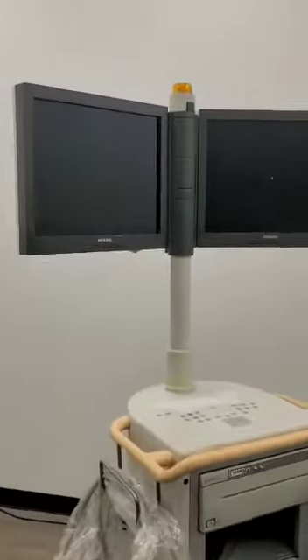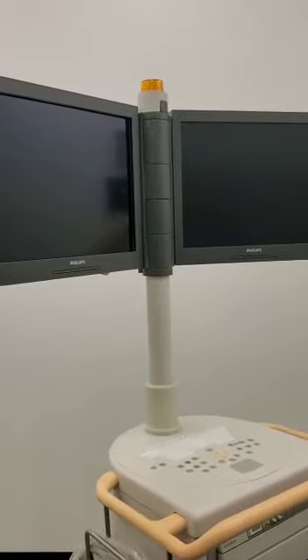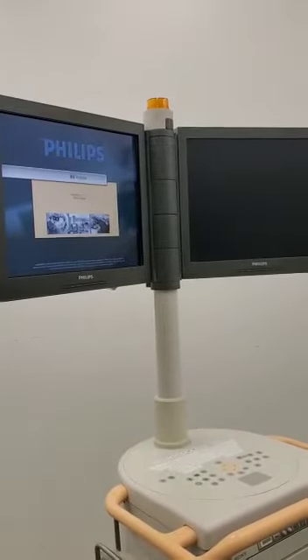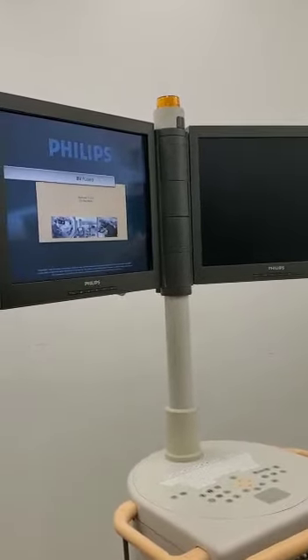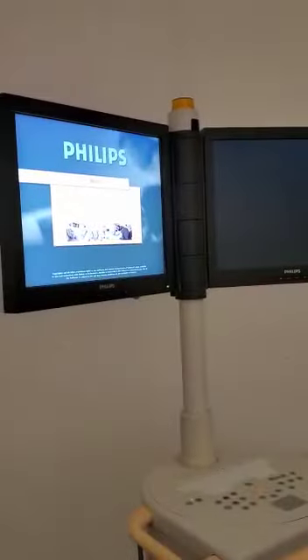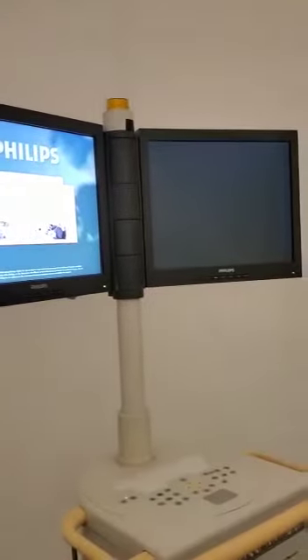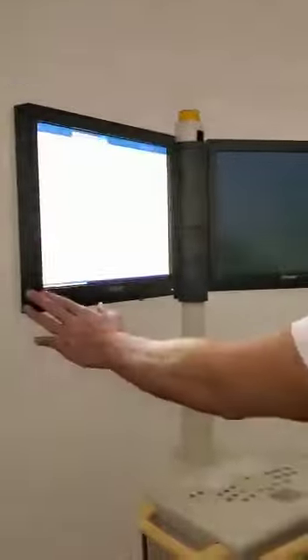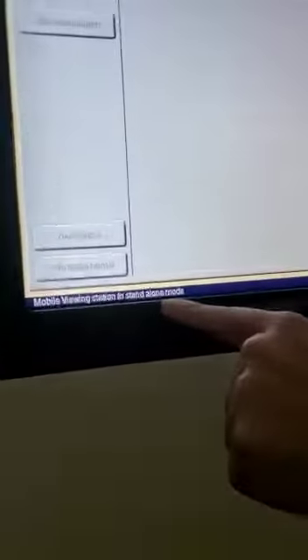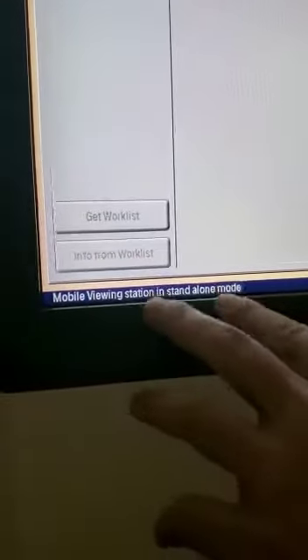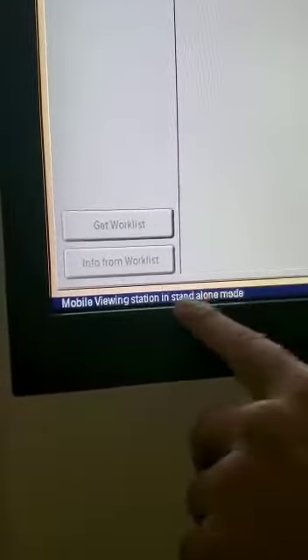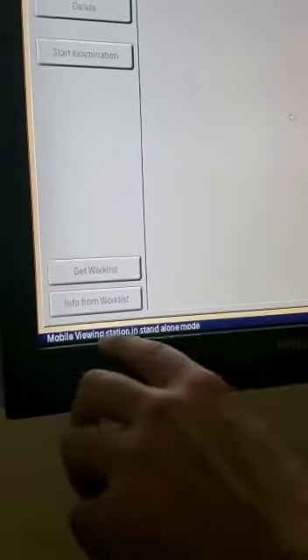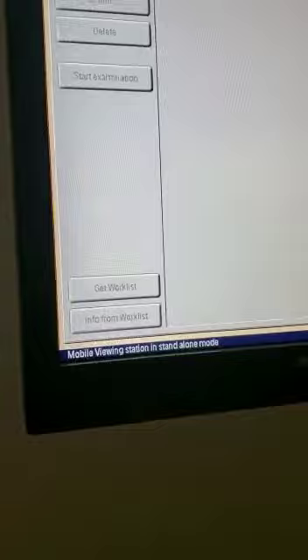The other way you know you're fully booted is to watch the workstation. The workstation always boots faster than the C-arm. As you can see, you have the software revision, after which will be followed by the patient registration screen. Now, if you look closely, it says mobile viewing station is in standalone mode. This message will not go away until the C-arm is fully booted. So that's the other way to tell that you're fully booted, is to wait for this message to go away.